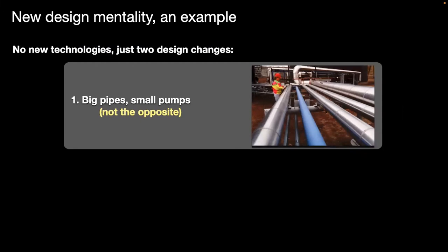So how fat should the pipe be to optimize the friction? Well, the standard textbooks all say to make the pipe just as fat as will repay its extra cost over the years from the saved pumping energy. But that's wrong because it leaves out the capital cost of the pumping equipment.